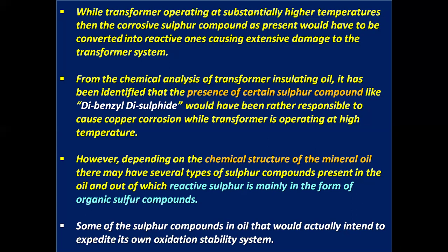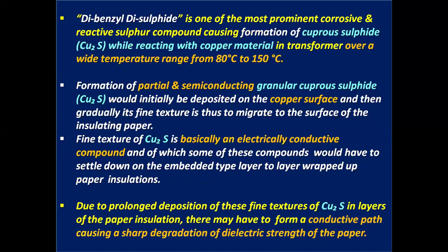However, depending on the chemical structure of the mineral oil, several types of sulfur compounds may be present in the oil, of which reactive sulfur is mainly in the form of organic sulfur compounds. Some of the sulfur compounds in oil would actually expedite its own oxidation. Dibenzyl disulfide is one of the most prominent corrosive and reactive sulfur compounds, causing formation of cuprous sulfide, Cu2S, while reacting with copper material in the transformer over a wide temperature range from 80 degrees centigrade to 150 degrees centigrade.